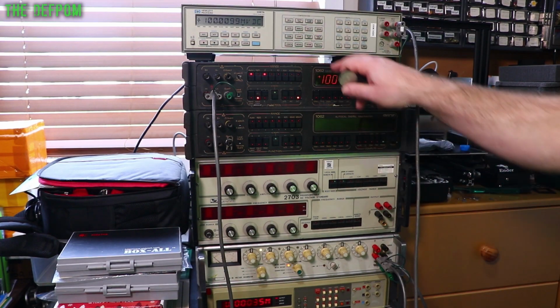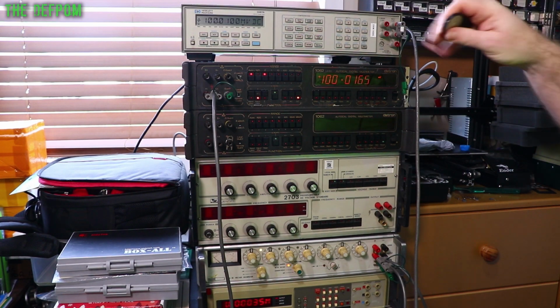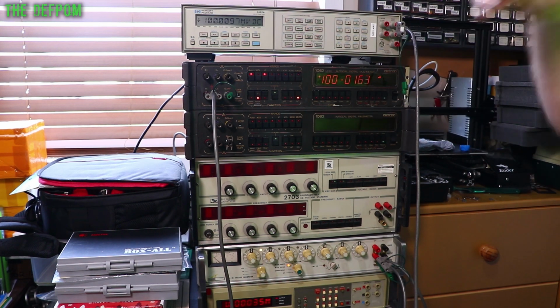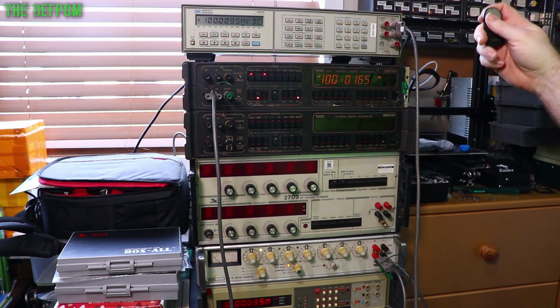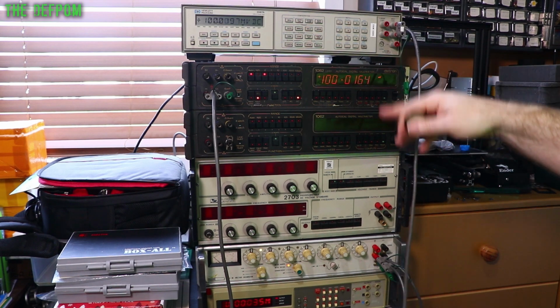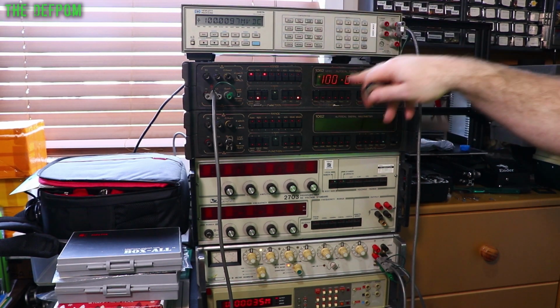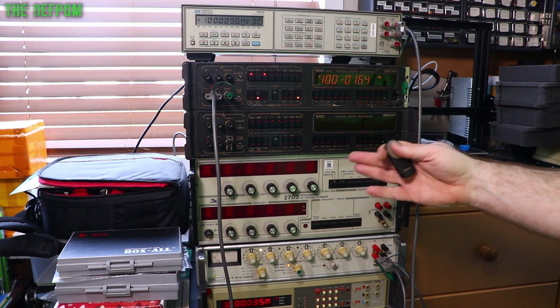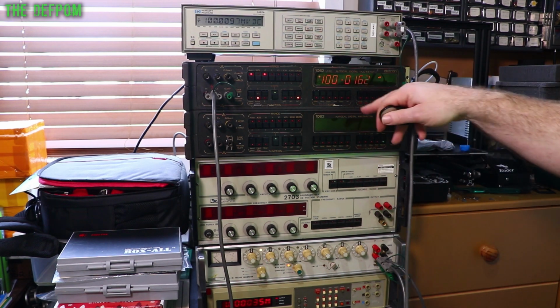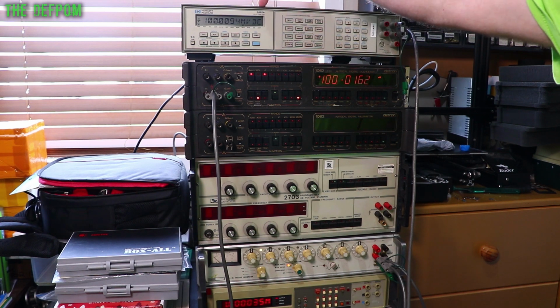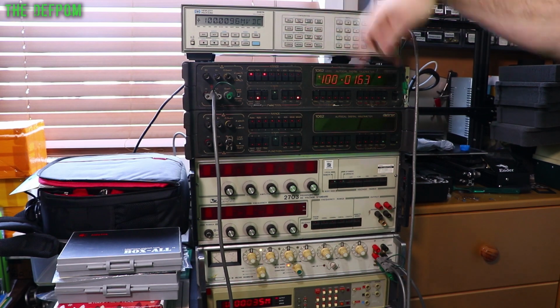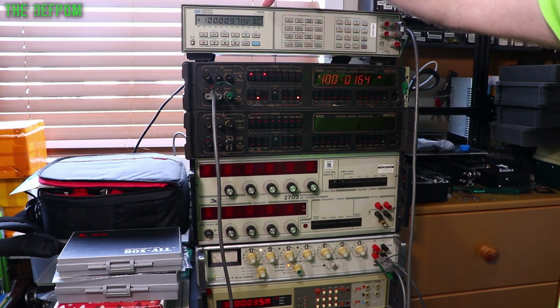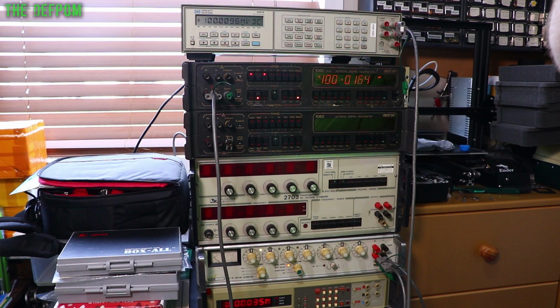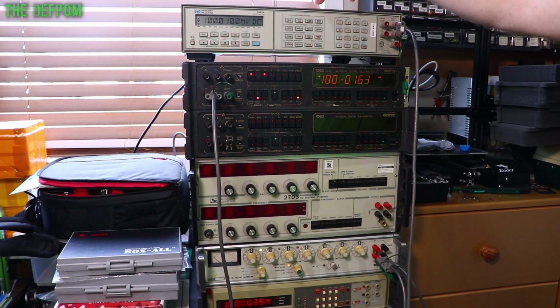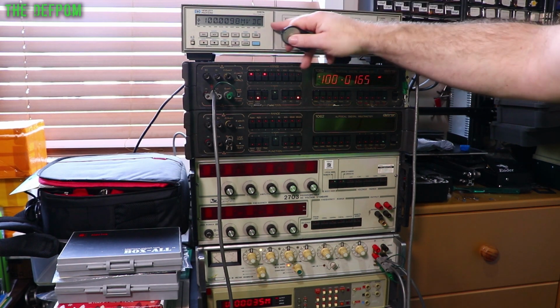So I'm going to do a calibration on this Datron now, and I'm only going to show you the DC section. I'm not going to show you the rest to give you an idea, because it takes such a long time to do. I haven't got the calibrate mode turned on yet, but I'm just going to show you what I've done. So I already did the basic calibration yesterday. It's kind of there, but it wasn't actually warmed up properly and that sort of stuff. So what I'm going to be doing is a calibration comparison against the HP 3457A showing 6.5 digits. Right, so they're basically like for like. Really, if you're doing a calibration, you'll be doing an extra digit, 10 times more resolution you've already got. So I don't actually have that, so we're just going to match it to this one.